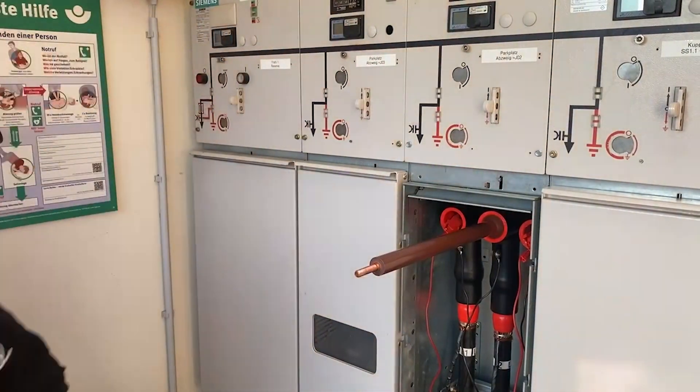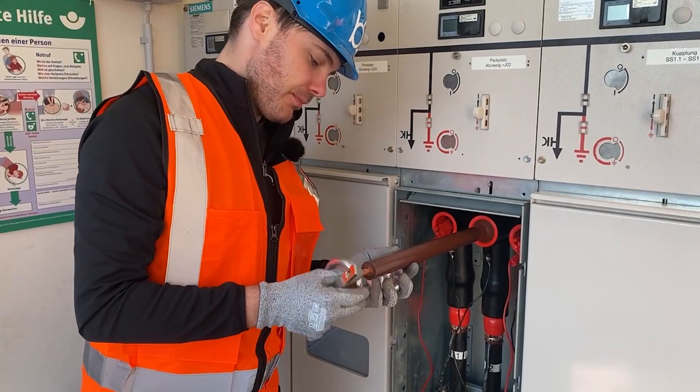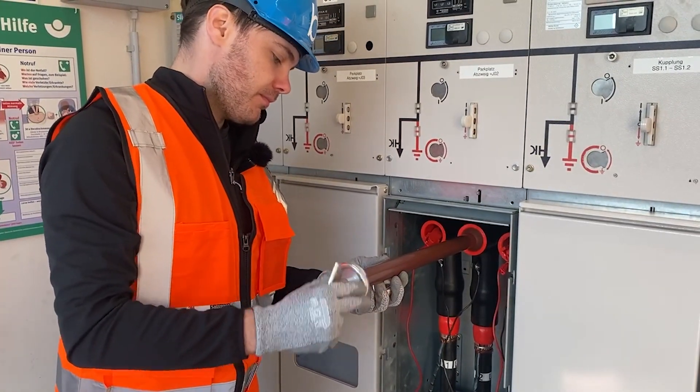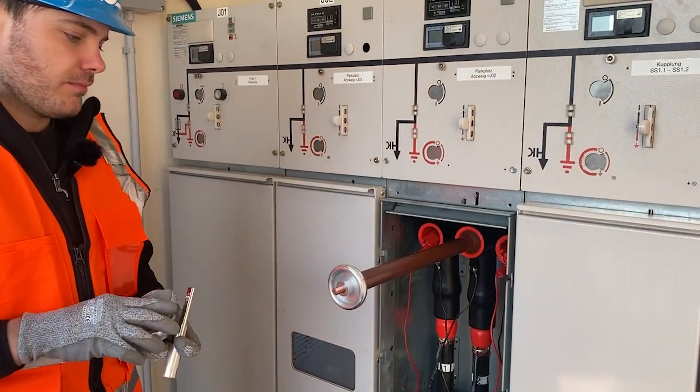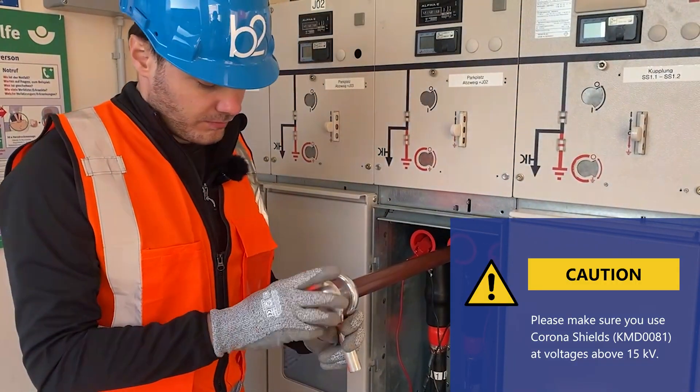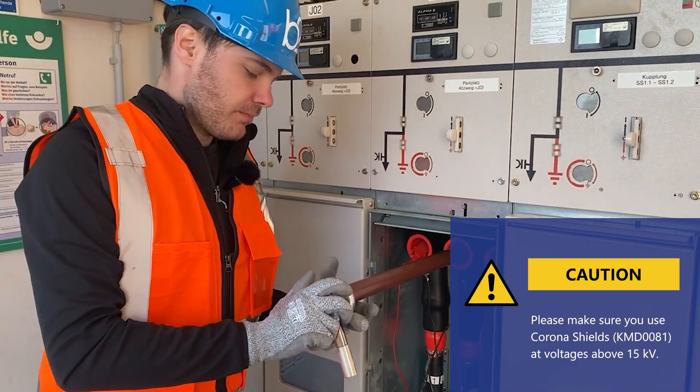Depending on your device under test, special testing adapters may be needed. In this case, we use a GIS testing adapter. For voltages above 15 kV, we recommend the use of corona shields.